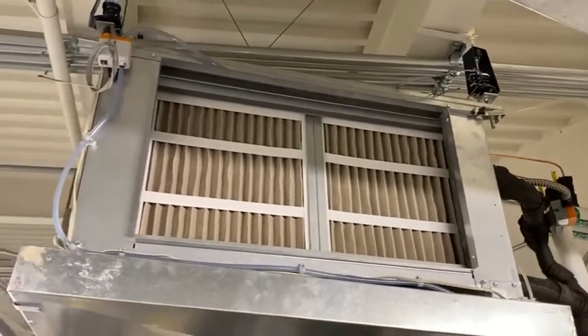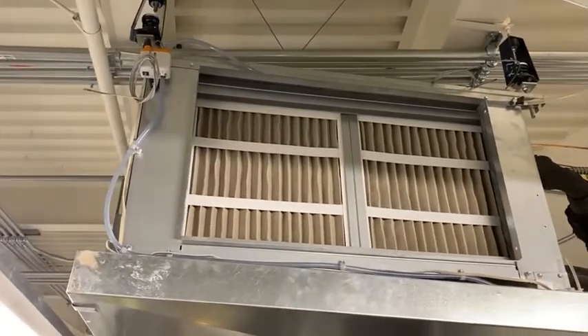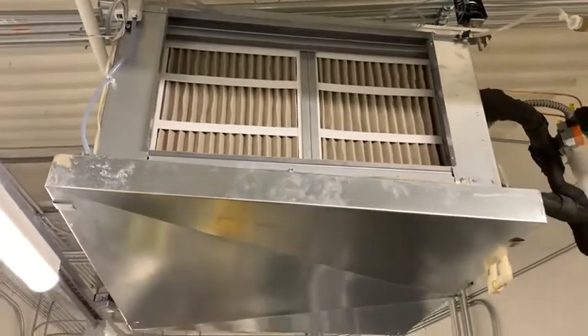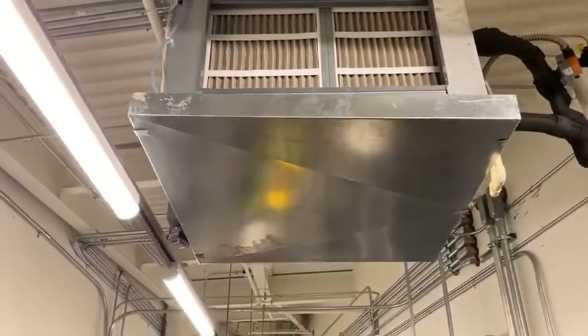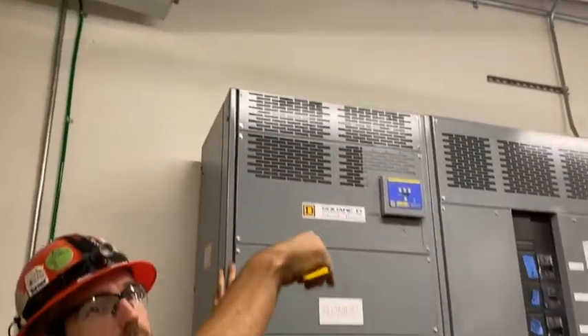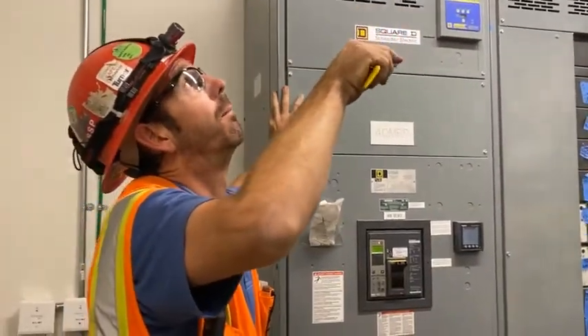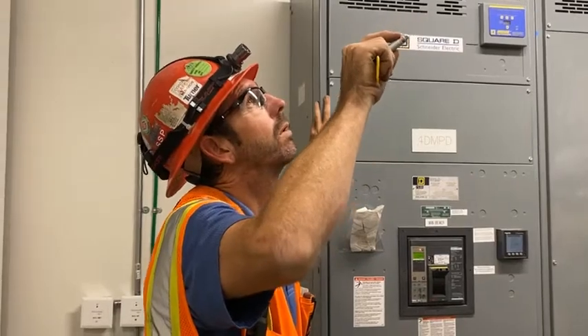Maintenance on this is mostly the filters. I'd say annually you want to look at the blower wheel. Make sure it's not getting dirty. Clean as needed. I'm hoping you're not cleaning the blower wheel every year. We'd want to get back into a filter program.